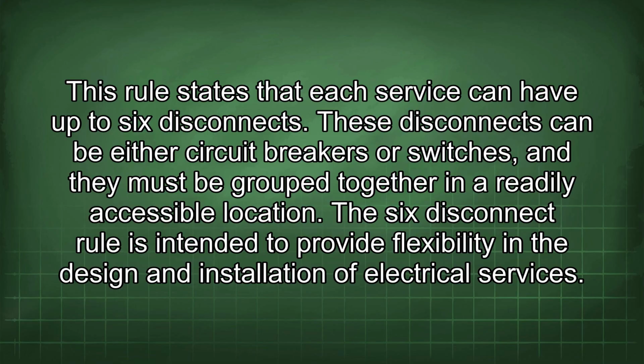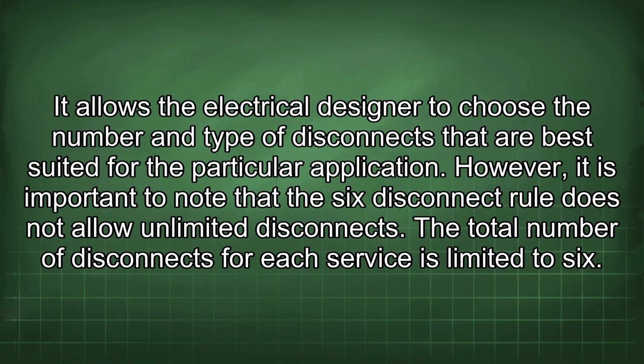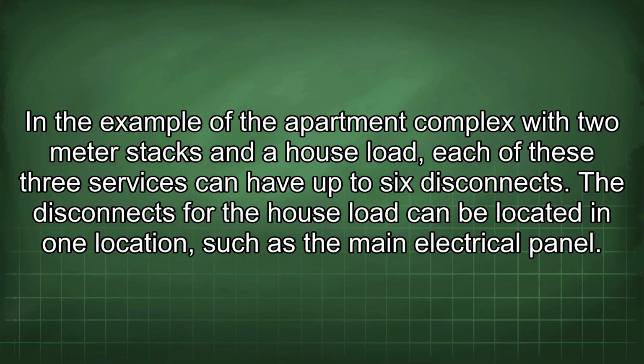The 6 disconnect rule is intended to provide flexibility in the design and installation of electrical services. It allows the electrical designer to choose the number and type of disconnects that are best suited for the particular application. However, it is important to note that the 6 disconnect rule does not allow unlimited disconnects. The total number of disconnects for each service is limited to 6. In the example of the apartment complex with 2 meter stacks and the house load, each of these 3 services can have up to 6 disconnects.